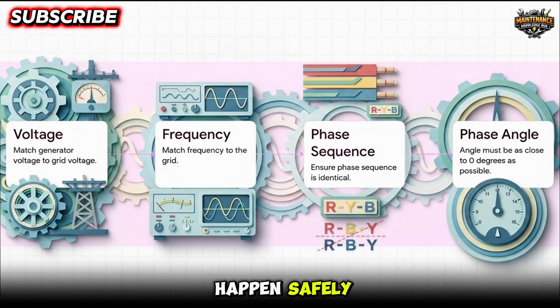To make this happen safely, operators rely on a mandatory, absolutely non-negotiable checklist. We call it VFPP. That stands for voltage, frequency, phase sequence, and phase angle. Every single one of these 4 parameters on the incoming generator has to mirror the live grid. Take phase sequence, for example, like red, yellow, blue. It has to be identical. If the grid is RYB, the generator simply cannot be RBY. Now, this is usually checked during commissioning and isn't something you'd casually change, but it is a foundational rule. Let's look at how we match the other 3, though.